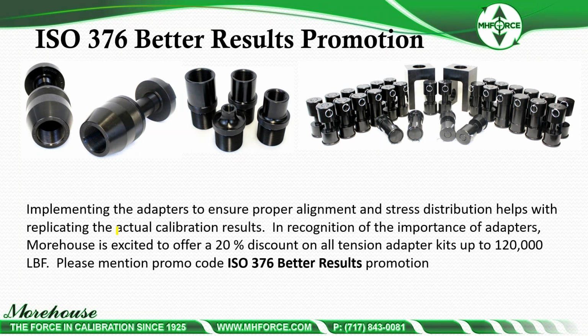Implementing the adapters to ensure proper alignment and stress distribution helps with replicating the actual calibration results. And if you're paying a lot of money for calibration and then using different things, or you're using a top pad made of aluminum that you're not sending in, and then we're using a hardened steel block, that's no good. You're going to have errors galore.